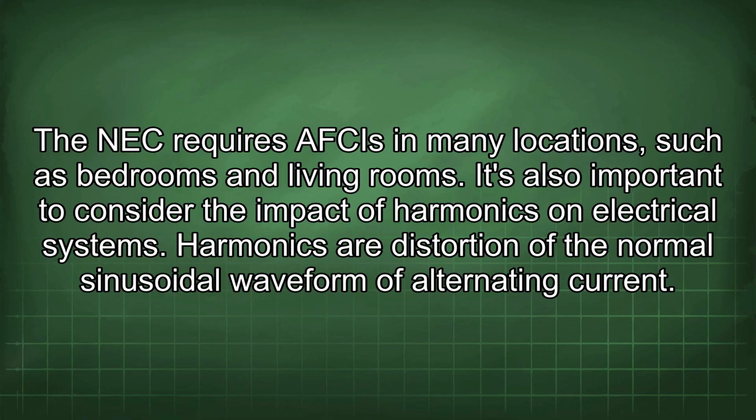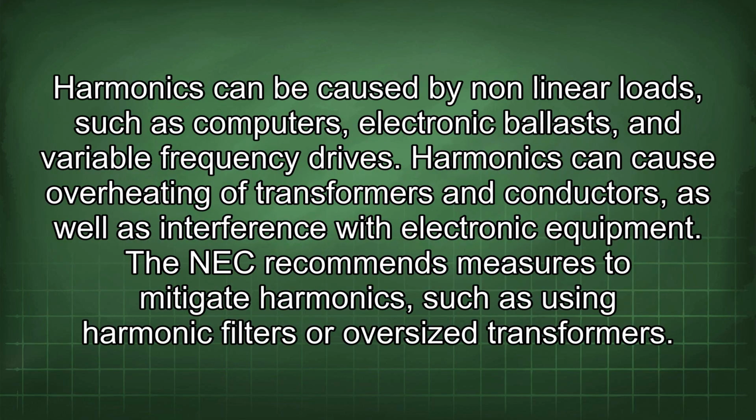It's also important to consider the impact of harmonics on electrical systems. Harmonics are a distortion of the normal sinusoidal waveform of alternating current. Harmonics can be caused by nonlinear loads, such as computers, electronic ballasts, and variable frequency drives. Harmonics can cause overheating of transformers and conductors, as well as interference with electronic equipment. The NEC recommends measures to mitigate harmonics, such as using harmonic filters or oversized transformers.